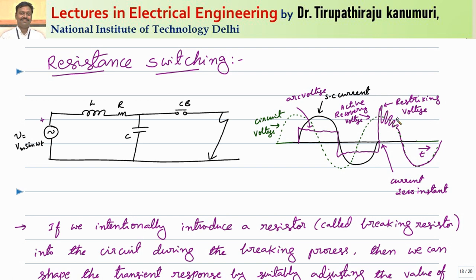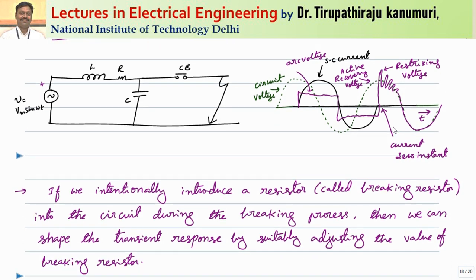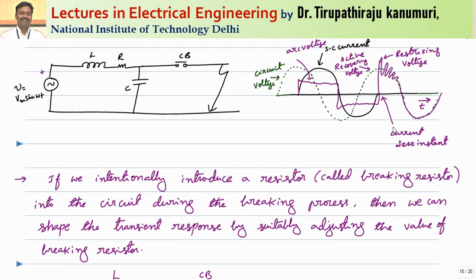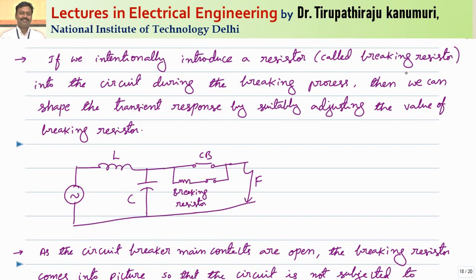This effect will be much more severe in cases of current chopping or capacitor current switching, which we will discuss in the next lecture. So, how can we overcome and suppress these high frequency oscillations so that the voltage across the contacts will only equal the active recovery voltage with no oscillations? To achieve this, we intentionally introduce a resistor across the circuit breaker contacts whenever the contacts are being opened.